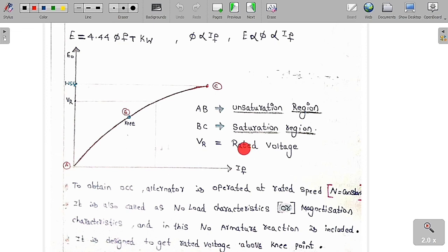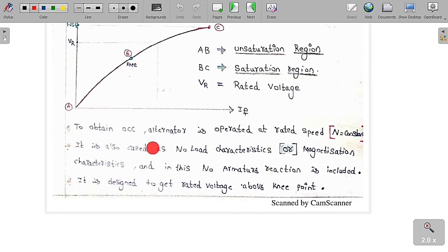Now let's see the consequences. In OCC, the open circuit characteristics, the alternator is operated at the rated speed, n equal to constant, meaning the prime mover should always be maintained at a constant, rated speed.